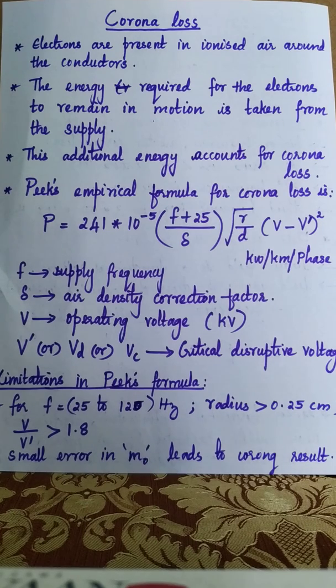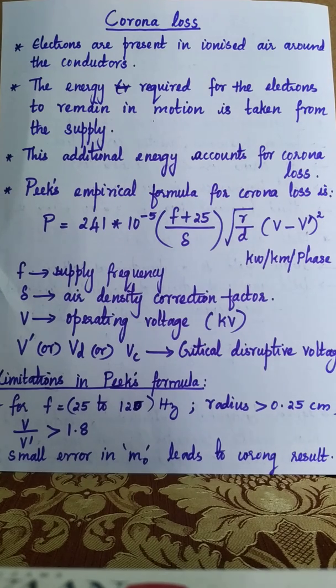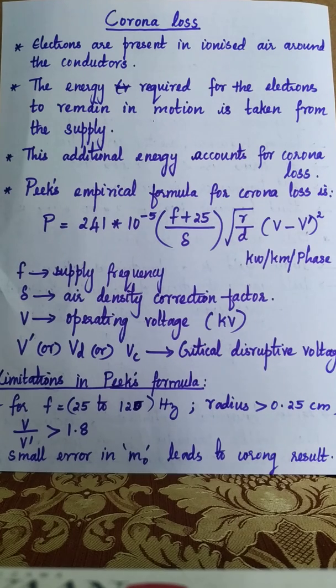Scientist Peek conducted experiments based on the factors responsible for corona loss and arrived at an empirical formula: P = 241 × 10⁻⁵ × (f + 25) / δ × √(r/D) × (V − V')² kilowatt per kilometer per phase. This is not a derived formula but an empirical formula resulting from experimental results.